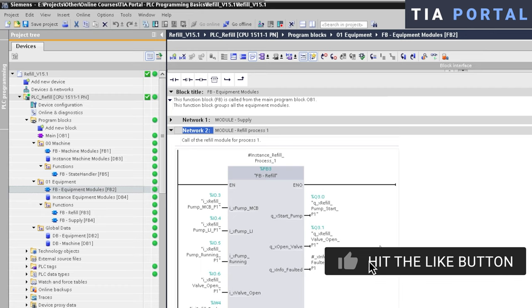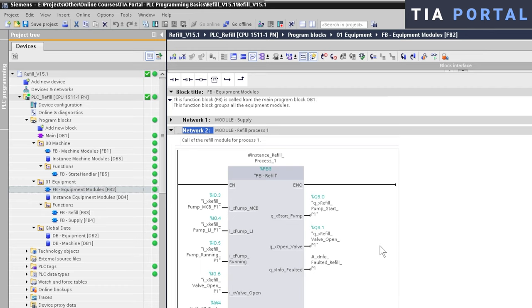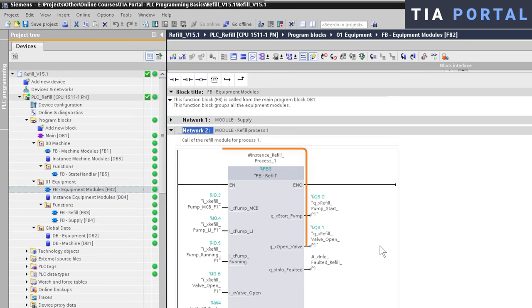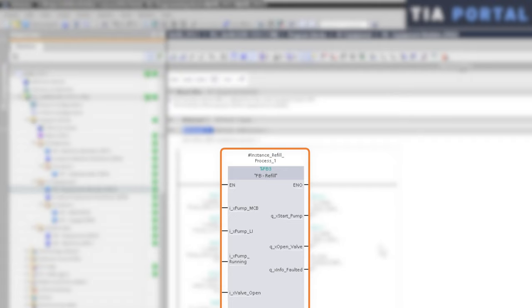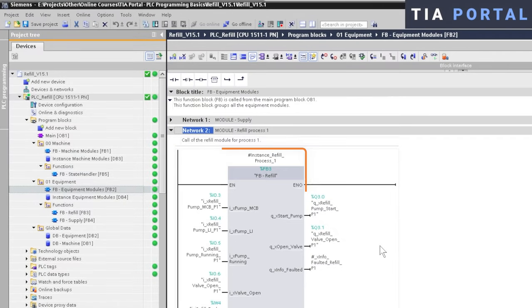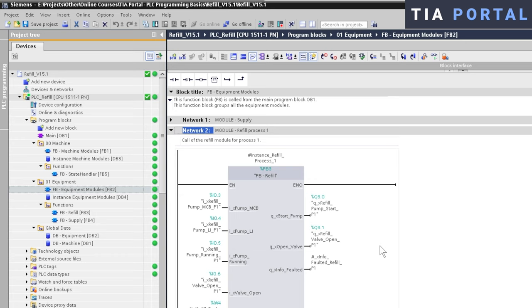A vital aspect of troubleshooting any PLC application is the ability to monitor logic while being online with the PLC. You get eyes on the application so you can see what's actually happening in real-time in your software. In this key area, we're specifically going to look at how logic is monitored inside a function block on both platforms, since monitoring of other blocks like OBs, DBs and FCs is very similar. If your function block is only called once in your user program, then there is no difference between these two platforms. Both will correctly display the monitored logic.